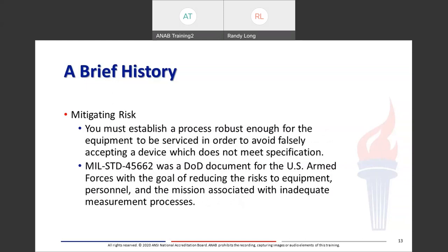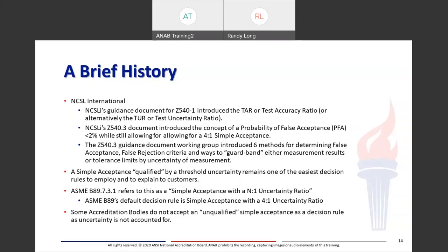The whole idea behind this is to mitigate risk. You have to establish a process robust enough for the equipment to be serviced in order to avoid falsely accepting a device which does not meet specifications. MIL-STD 45662 was a DOD document for the armed forces with the goal of reducing risk to equipment, personnel, and mission associated with inadequate measurement processes. NCSL International had a guidance document for Z540-1 which introduced the concept of TAR, taking that same MIL-Standard concept of reducing the uncertainty to 25% of the tolerance — and hence was born the 4-to-1 uncertainty ratio.